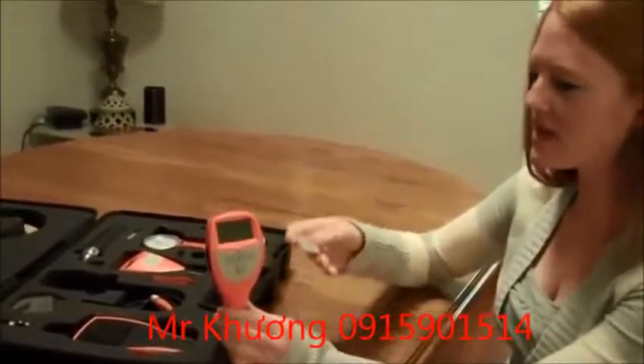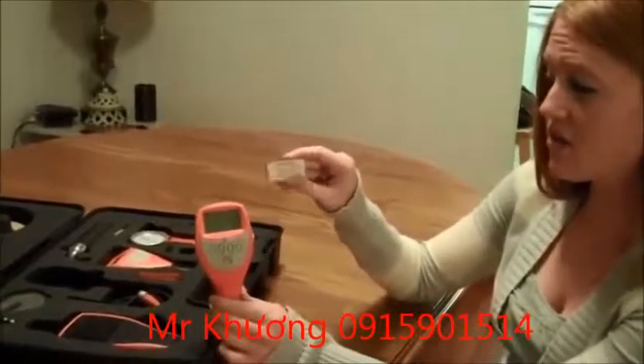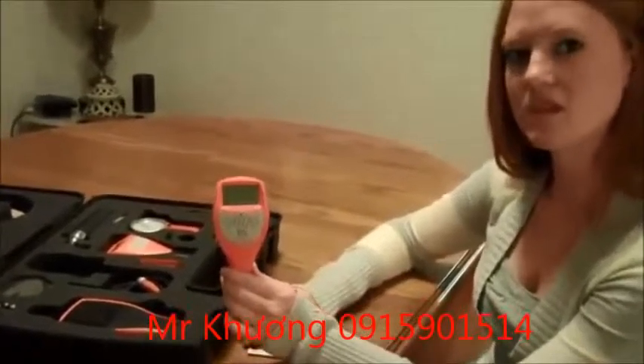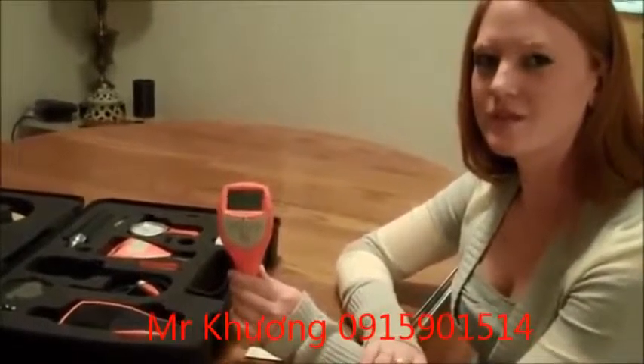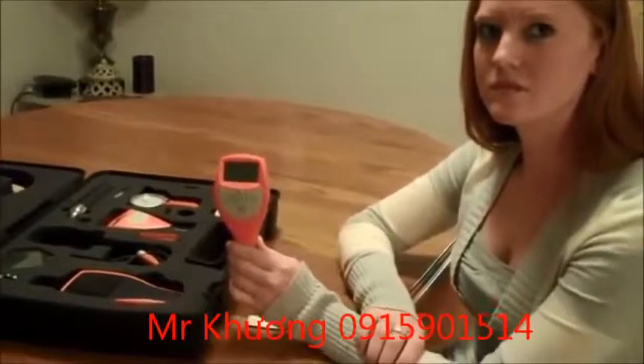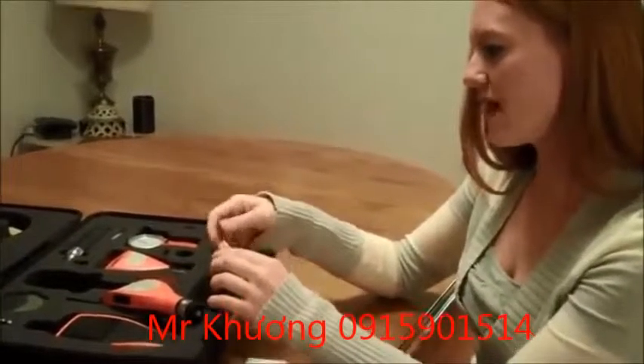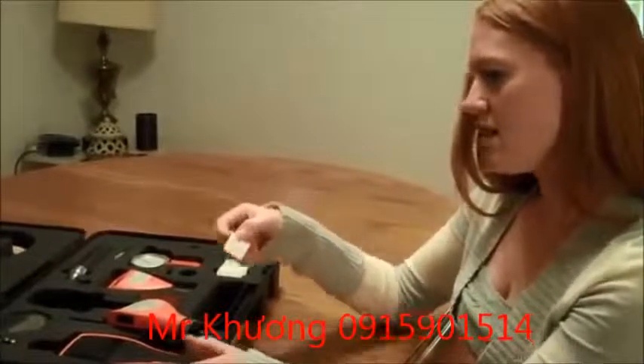All right, so first we're going to start with our base, which for this purpose we're using ferrous zero plates. Now, if you have access to an uncoated part that you're going to be actually measuring out in the production area, that would be the best thing to use for your uncoated base during calibration. But if not, you can just use a test plate like Kelly has here. All right, and on top of the test plate, I'm going to put my shim.